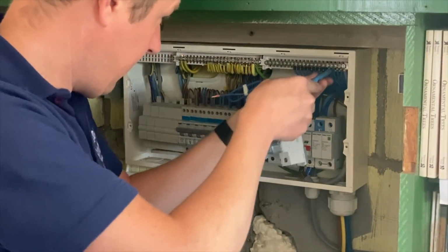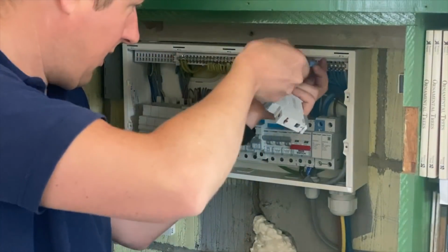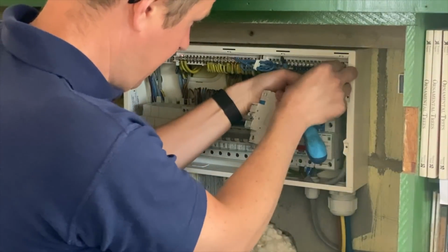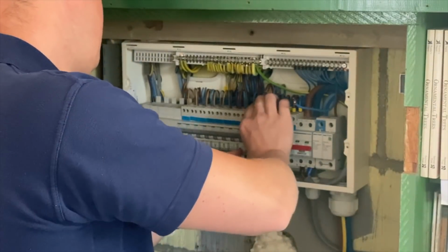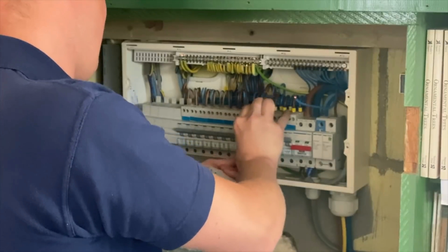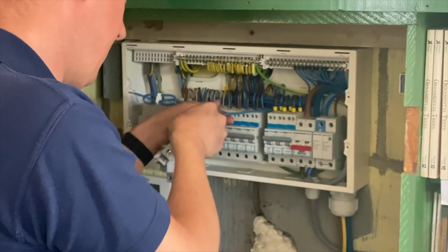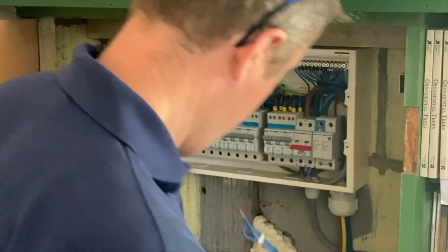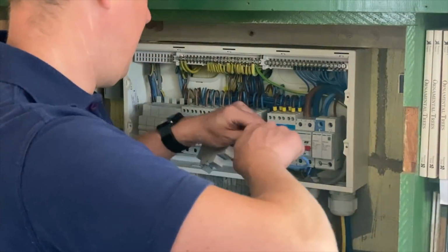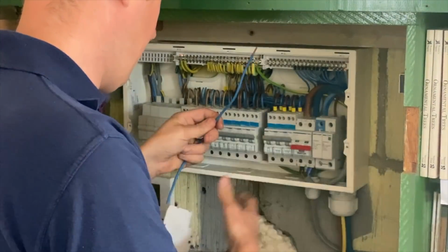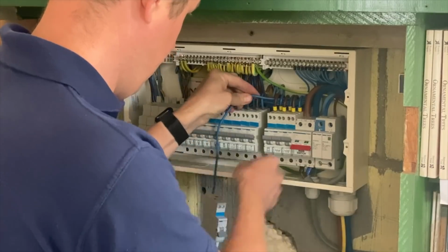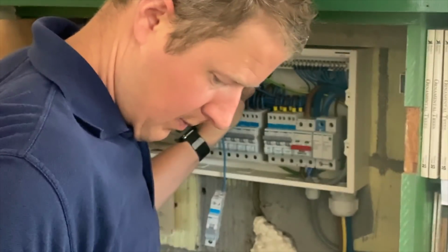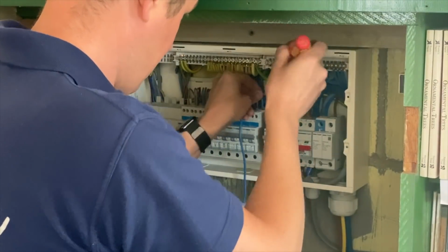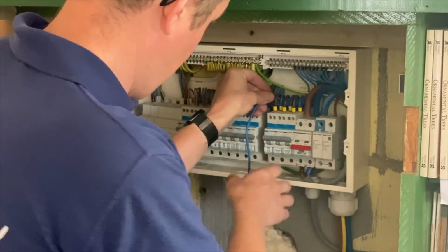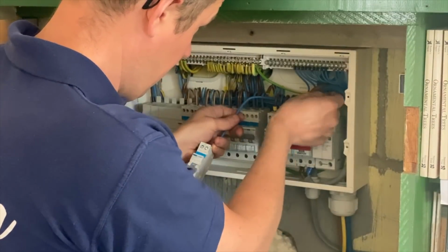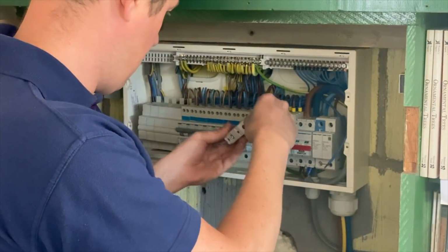And I'll need to disconnect this, so it's the fourth one along. 1, 2, 3, 4. Disconnect the neutral tail. Typical, isn't it? That it has to have one dodgy one that messes up my whole nice, neat array. But anyway, there we go. So that will pull out. And then, I bet you I'll change this and it'll still be doing the same, and it will be some kind of problem on the actual circuit rather than the RCBO, but there's no way to really know. That's the trouble. I mean, the insulation readings are okay on this circuit, so all I can think is that it's a faulty RCBO.